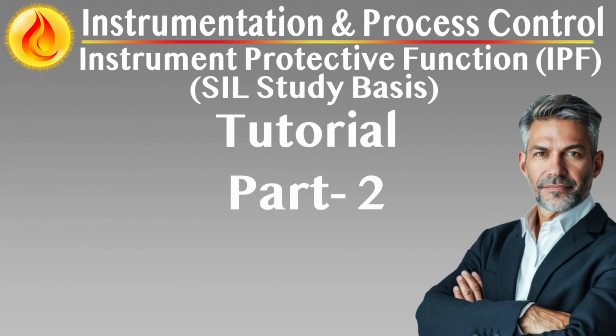Personnel health and safety consequences in SIL determination, prioritizing human impact in IPF classification. When assessing the need for an instrument protective function, IPF, consequences to personnel health and safety are considered the highest priority. Unlike asset or environmental impacts, risks to human life carry the lowest tolerance thresholds and directly influence the minimum required safety integrity level, SIL.